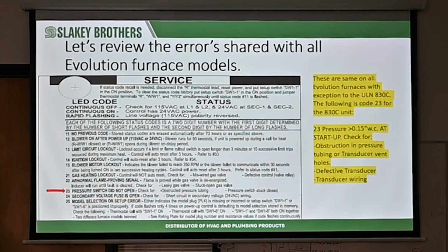If the gas valve is leaking gas through and is keeping the flame on a little bit longer, it means replace the gas valve. If there is no flame there, you do the traditional clean up the flame sensor and all that. Make sure the flame sensor isn't dirty or corroded or nothing. And then if it continues to do it, it just means there's something wrong with the circuit board as well at that point. So it can only be a few things. The abnormal flame proving, if there is no flame there, there is nothing wrong with the flame sensor, you replace that.